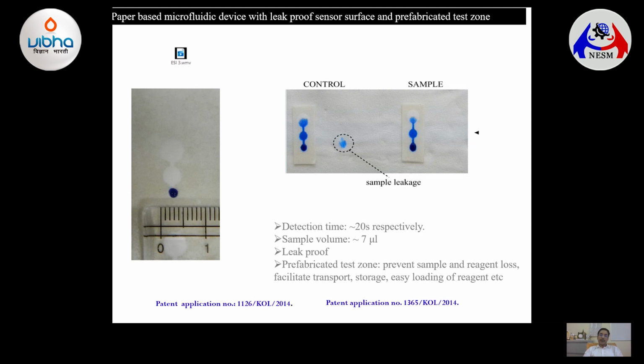Now, one of the important issues is that when you use paper, the sample leaks out from the rear side of the paper. To prevent that, we have developed a technology so that when you load the sample on the surface of the strip, it will not leak out from the rear side. Additionally, we have developed a technology where the test zone, where the reagent is, can be separately prepared and, at the time of the test, put on the surface of the paper.